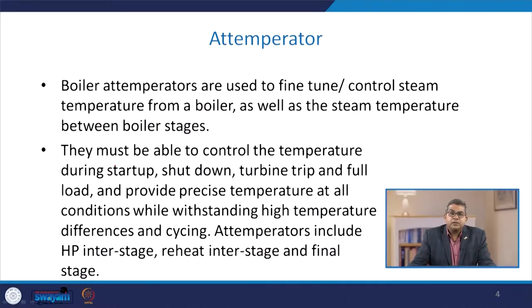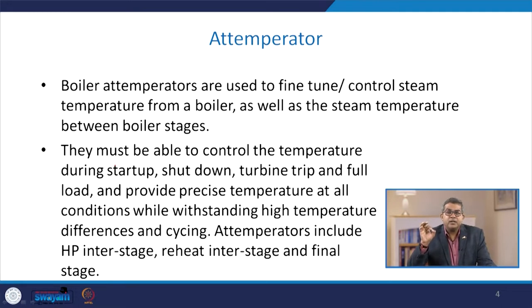Sometimes different types of boiler stages are used, so attemperators control steam temperature. The desirables in attemperators are: they must be able to control temperature during startup, shutdown, when a turbine may trip, and when the turbine runs on full load — providing precise temperature at all conditions while withstanding high temperature differences and cycling. This includes high pressure inter-stage, reheat inter-stage, and final stage.